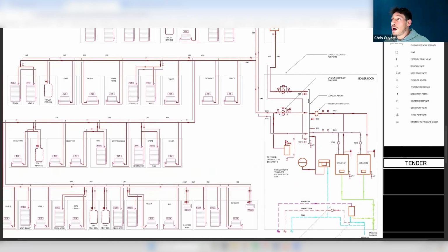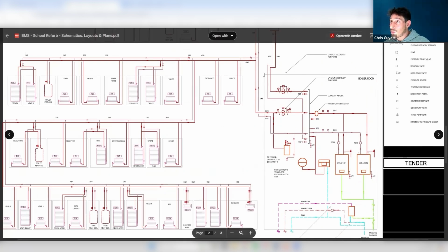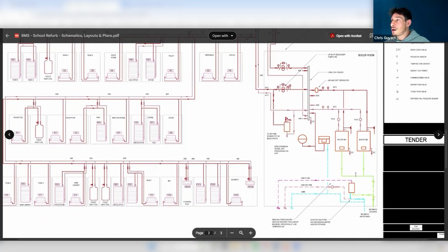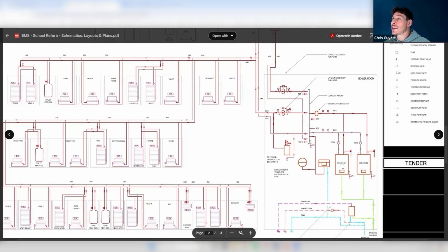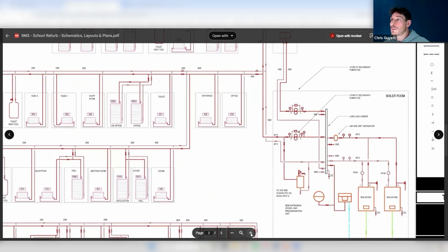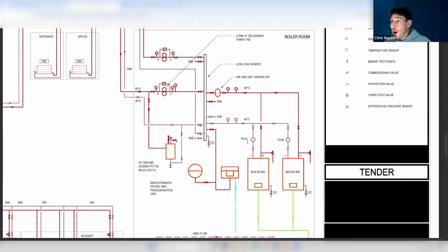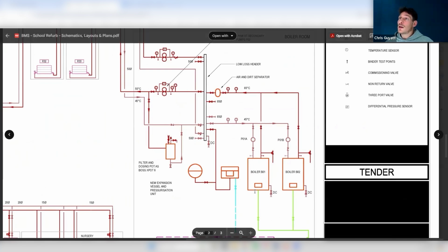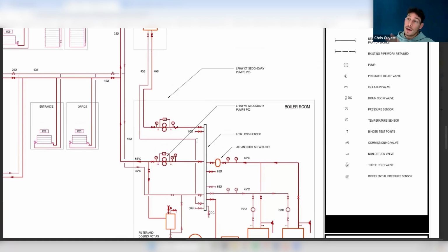So this is the plant room, and this grey box indicates what's in the plant room. We've got two boilers that we're controlling, and the main incoming gas, so the BMS will control the gas on and off based on certain conditions. Looking closer, we've got our boilers, pumps for each boiler, T for temperature sensors, and P for pressure sensors—this is known as the primary side. The primary side is what you see before a low loss header; the secondary side is the other side of it, where we've got more pressure sensors and these two pumps here, like a duty standby arrangement, Josh, like we were talking about yesterday.